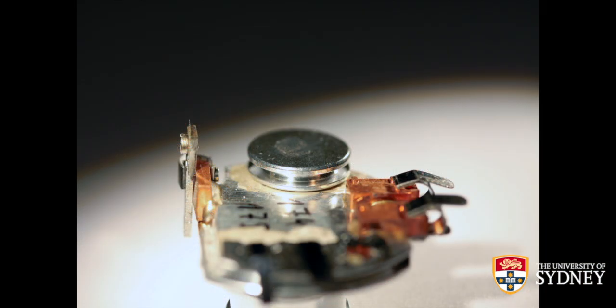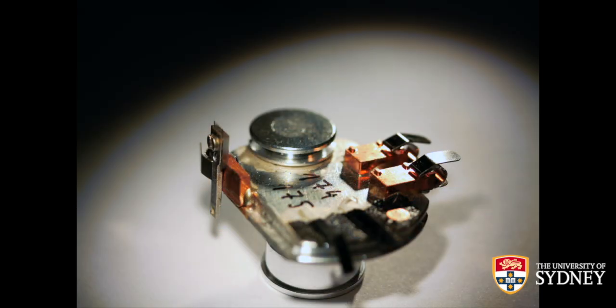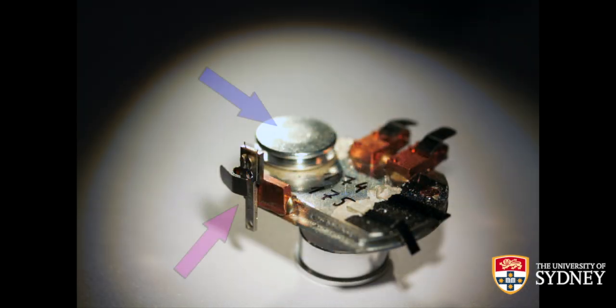The basic assembly for the lift out is shown here. So that's my little stage that I've got for lift out. With the blue arrow, you've got the sample marked, and with the pink arrow, you've got the holder marked.